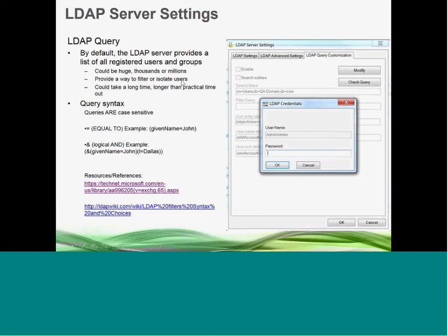So let me give you an example. If in your process or your machine, your plant floor, there's no way the administrative assistants or office workers are ever going to come out to the plant floor and log into one of your computers, you might want to filter those out of the equation and not allow them to log on to the HMI that's running the machine. So in this way, you might want to add the operator groups, the supervisor, control supervisor, maintenance staff, production, whatever makes sense. Enable those groups.